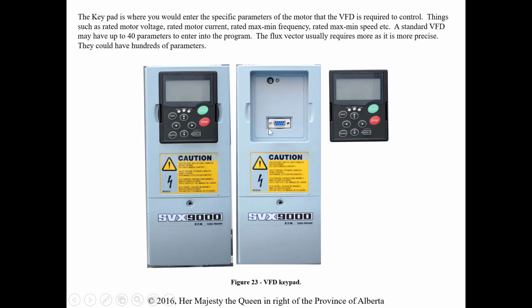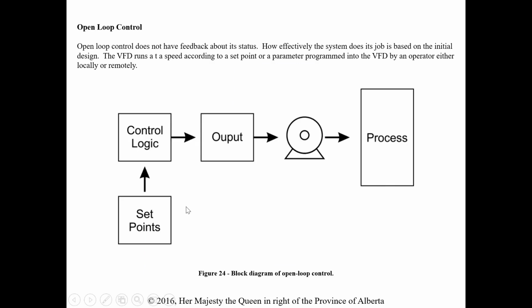The keypad on the VFD is where we can enter the specific parameters required. You can make changes on the fly if it's on this local control. Local meaning we're touching the screen that's right attached to it. Remote meaning it's happening from somewhere else. Things such as rated motor voltage, current, frequency, maximum frequency, minimum frequency, max speed, minimum speed, all that can be entered in there. A standard VFD can have up to 40 parameters. The flux vector usually requires more. It could have up to hundreds. Okay, so again, way more specific control, but again, I would assume the cost would be quite a bit more in that aspect as well. So then we start talking about different types of control.